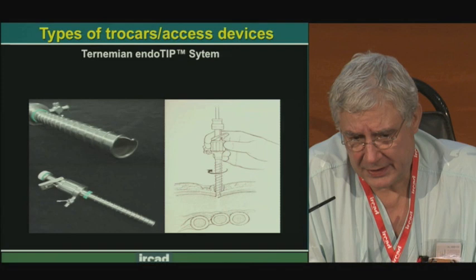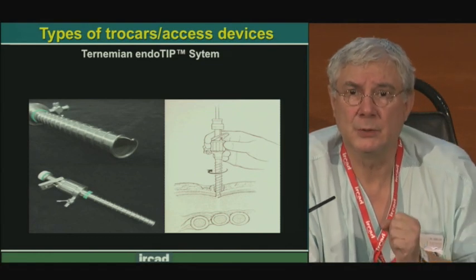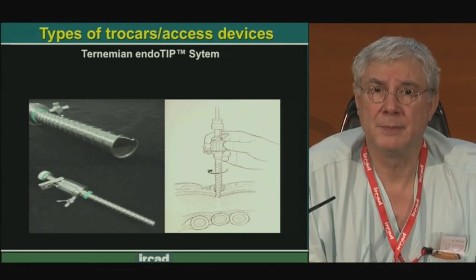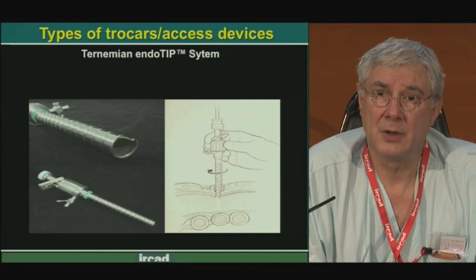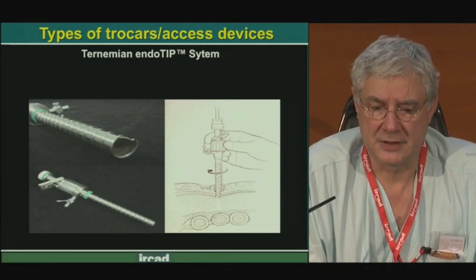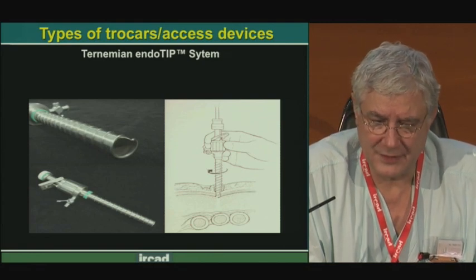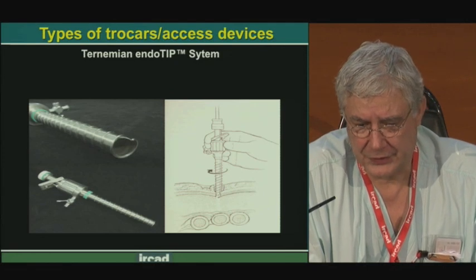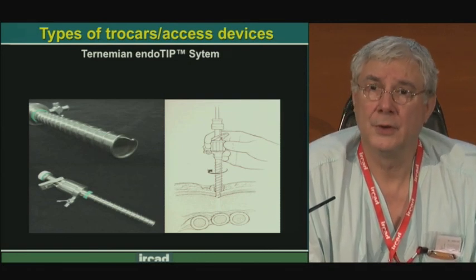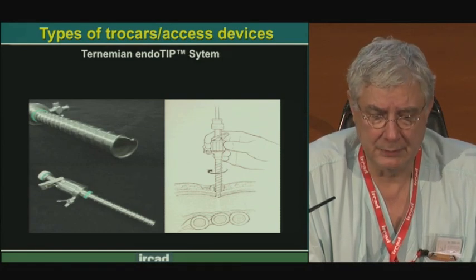Another trocar developed and designed by industry is the optical trocar — we can see what we are doing as we introduce the trocar through the abdominal wall. This reusable trocar was developed by a Storz company and is called the Ternamian trocar tip system, designed by surgeon Ternamian working in Canada. It is a trocar that is screwed in with a small knife at the extremity. As we screw the trocar, we progressively cut through the different layers under video control, with a video camera inside the trocar allowing us to see the different layers.